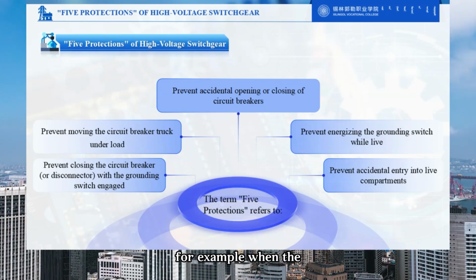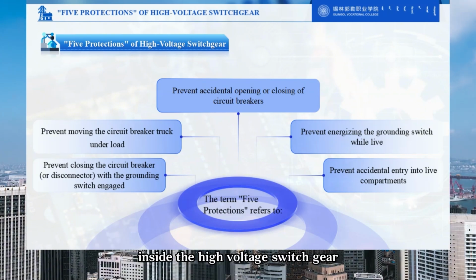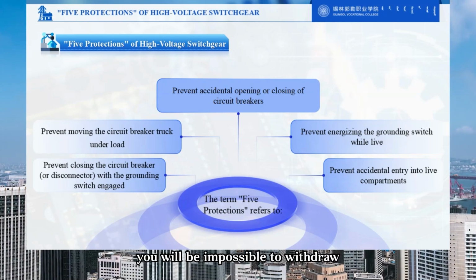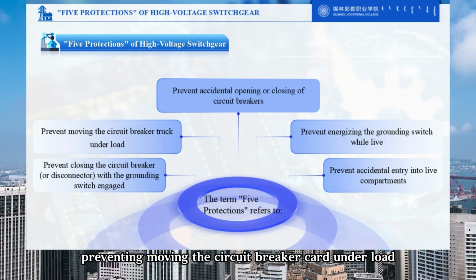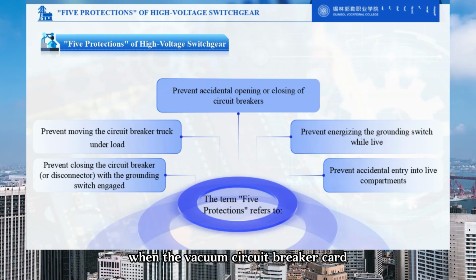For example, when the vacuum circuit breaker inside the high voltage switchgear is in the working and closed state, it will be impossible to withdraw the circuit breaker truck from its working position. Preventing moving the circuit breaker truck under load. When the vacuum circuit breaker truck inside the high voltage switchgear is closed in the test position, the circuit breaker truck cannot enter the working position.